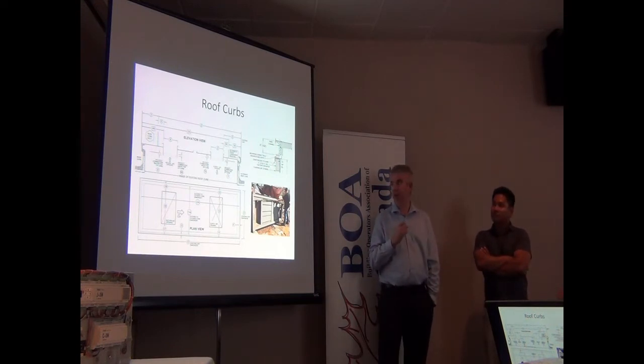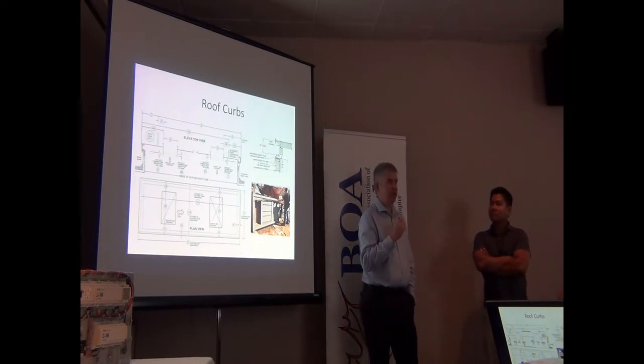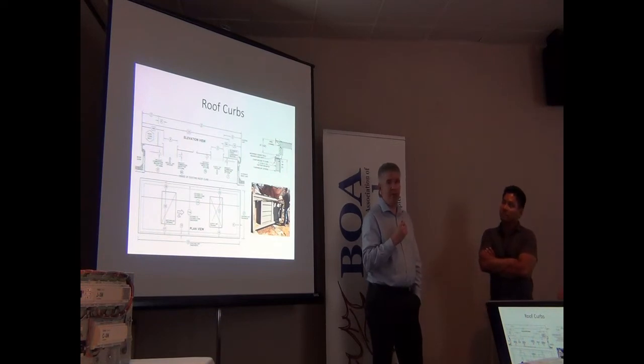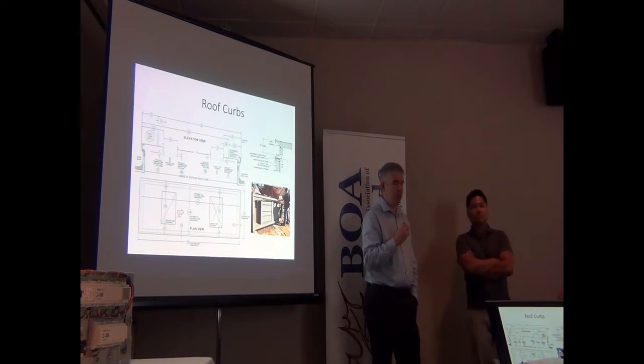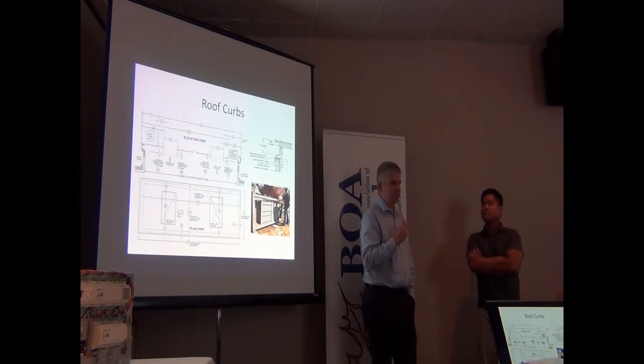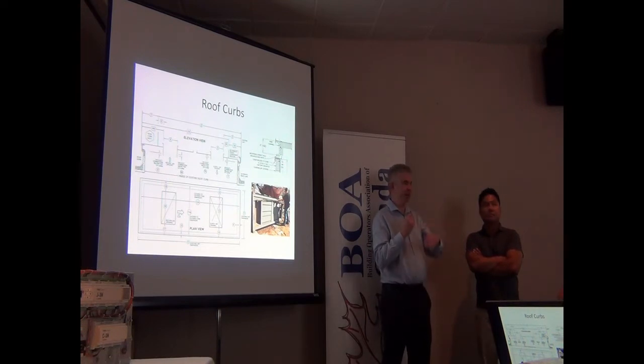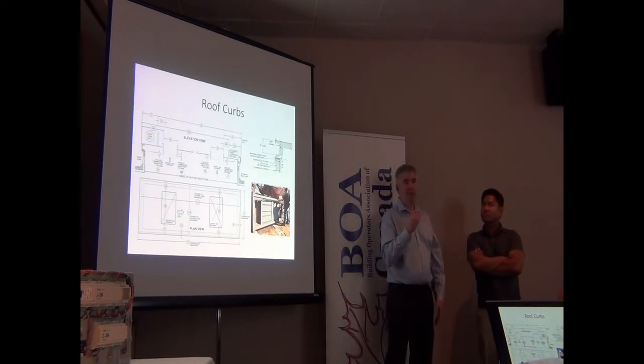One thing that can happen when retrofitting units, and I've seen it happen a number of times, is you can end up with adapter curbs that are 4 feet tall, awkward in size, which makes serviceability very difficult. I was up on the roof of an apartment complex retrofitted about 2 months ago, and now the unit's 6-7 feet in the air, requiring a ladder while overlooking an 8-story drop about 5 feet next to you. It used to be level, but because they needed a curb to make it work, it's now very difficult for everybody to service.